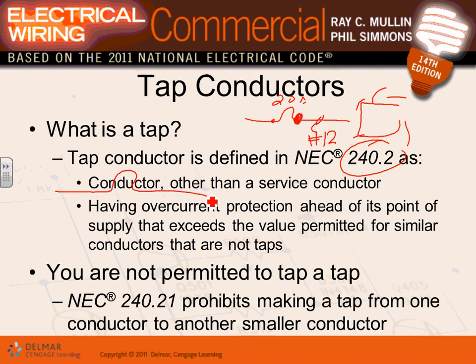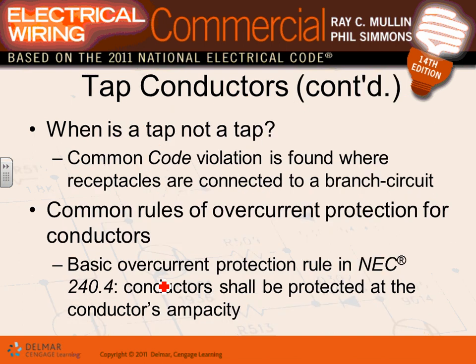The tap is where you take a 100 ampere conductor and you grab from here and put your conductor right here. Let's say 10 amps, 15 amps here, and you feed a piece of equipment here. Can you see the equipment receives its power here? If you put 10 feet here, that's a 10-foot tap. If you make it 25 feet, that's a 25-foot tap. So here's 100 amp, and here's my conductor, number 14, for example, and the overcurrent device ahead of it is 100. There are rules in 240.21 that talk about taps. I'm going to summarize them in a second. The rules for tapping, I'll summarize them in a second.